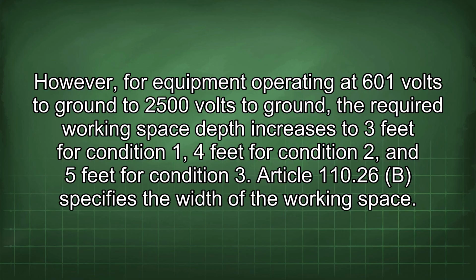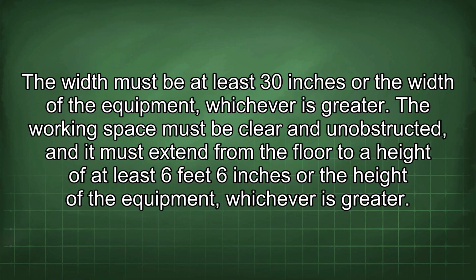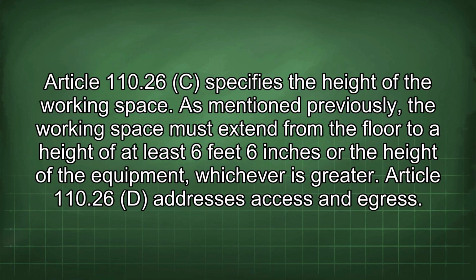Article 110.26b specifies the width of the working space. The width must be at least 30 inches or the width of the equipment, whichever is greater. The working space must be clear and unobstructed, and it must extend from the floor to a height of at least 6 feet 6 inches or the height of the equipment, whichever is greater. Article 110.26c specifies the height of the working space. As mentioned previously, the working space must extend from the floor to a height of at least 6 feet 6 inches or the height of the equipment, whichever is greater.